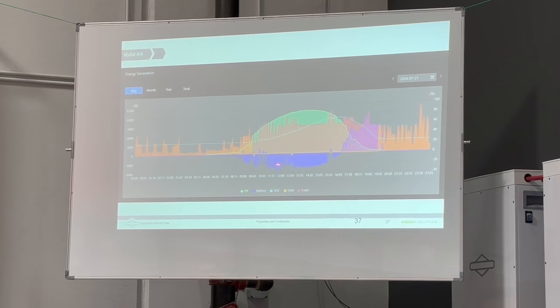But you've got PV coming throughout the day. You'll see the battery goes negative here. That means the battery's in a state of charge when it's negative. There are times when the battery goes positive. It looks like there are a few times where you've got big loads that kick on and draw some power out of the battery. But for the most part, during the day when that solar is there, it's more than enough for the loads, and that means the battery's in a state of charge. So the solar is at green. Whenever it's above the orange line, that means you're either sending power to the battery and the battery's charging, or you're sending excess power back out to the grid if you have an interconnection agreement.